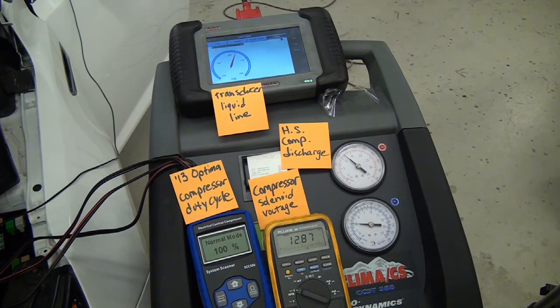The compressor discharge high side has gone up even further and looks like it's sitting at about 165. Same thing with the transducer, which is reading the high side liquid line. That's gone up to about 152. So what we're going to do now is go back down to our low heat load condition. So we're going to turn the blower speed back down to low, close the windows, and change the setting from outside air to recirculate.